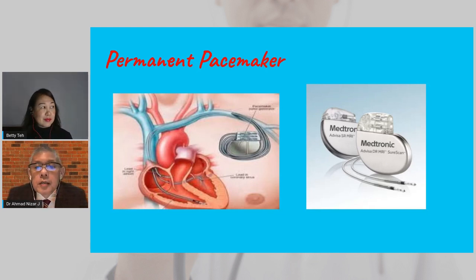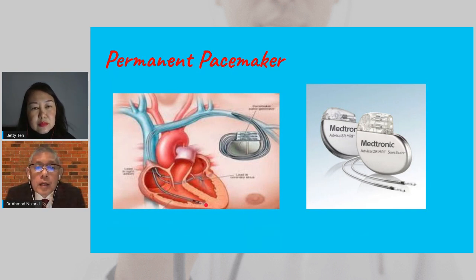But a pacemaker system, like any chain, can be troubled by the weakest link. So in a pacemaker system, you have the generator, which is the device that we place at the left shoulder usually. That's connected to the lead, and that is actually implanted in the heart. So you have three components of this: the generator, the lead, as well as the person's heart. Usually it's the lead that is the weakest point, and that is an issue that can be overcome by this new type of pacemaker.